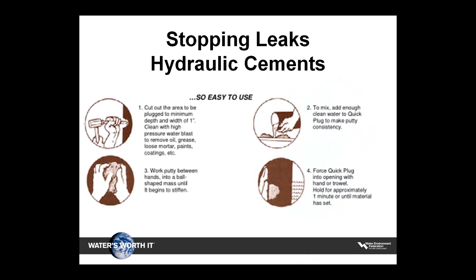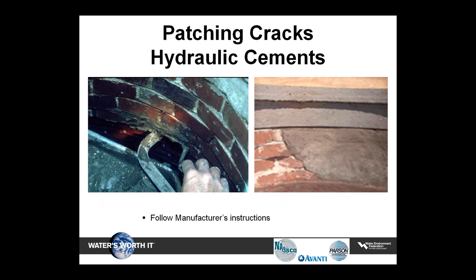Stopping active leaks is also a key element that will affect the bond of the lining product to the manhole. Cementitious lining materials are not designed to be applied where active leaks are visible — their set times are too long to stop moving water. Use of fast hydraulic cements and urethane, acrylic, or acrylamide grouts is necessary to establish a leak-free manhole surface. Cementitious patching materials can be used to fill in gaps, voids, or holes that may be excessively deep prior to installation of the cementitious lining. Set times for patching materials are usually in the 30-minute range.